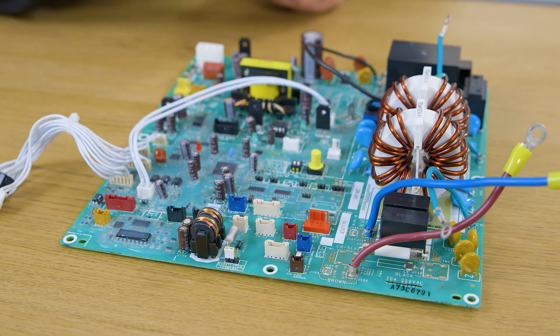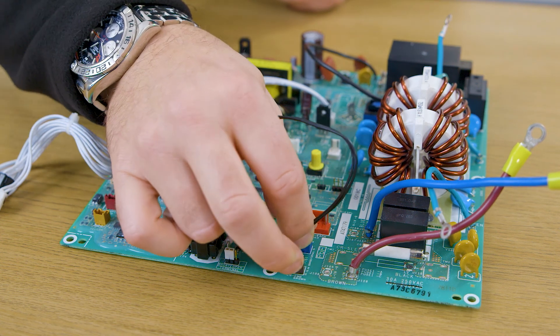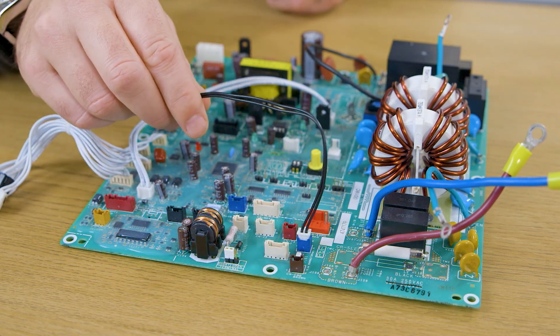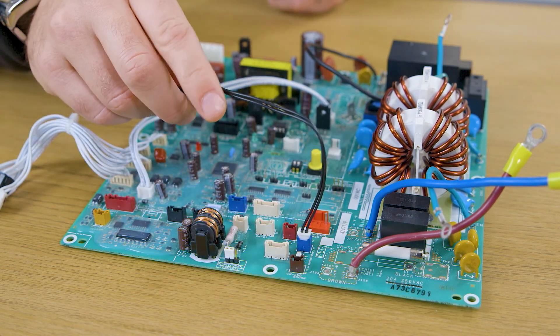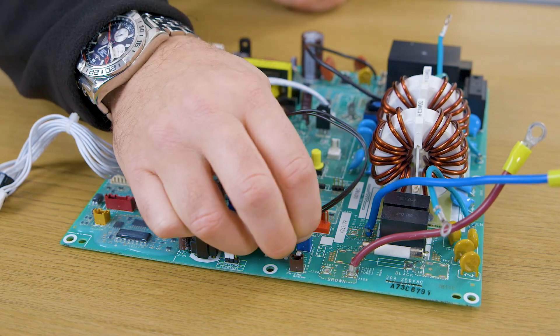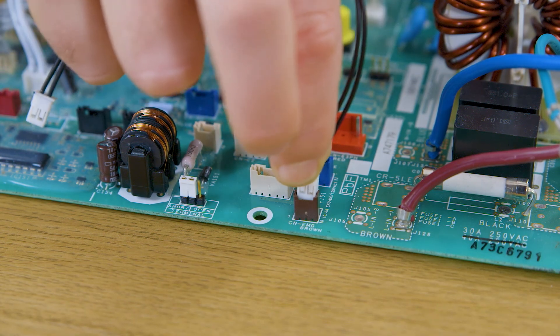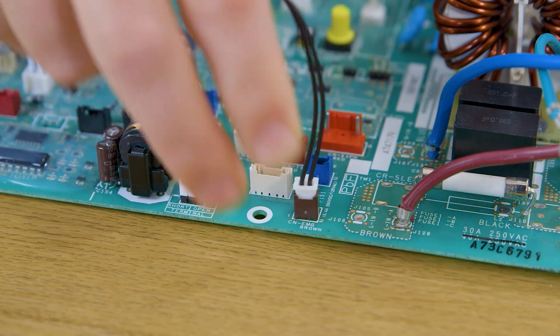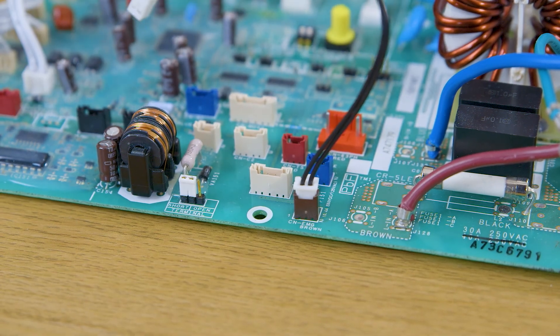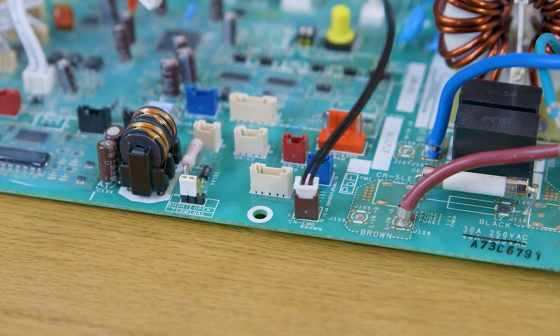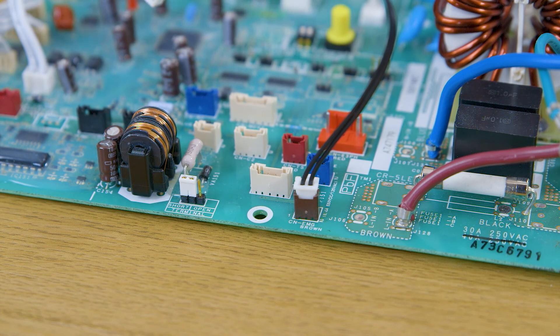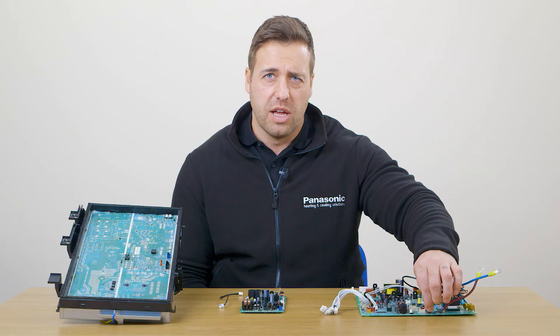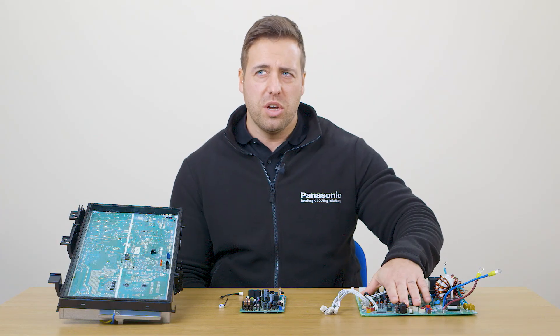On the outdoor PCB, the U1, U2 plug for your comms plugs into the blue connection, the OC. You can simply unplug it from the blue connection, plug it into the brown connection underneath on CNEMG, which stands for emergency. That's on the outdoor board facing you.